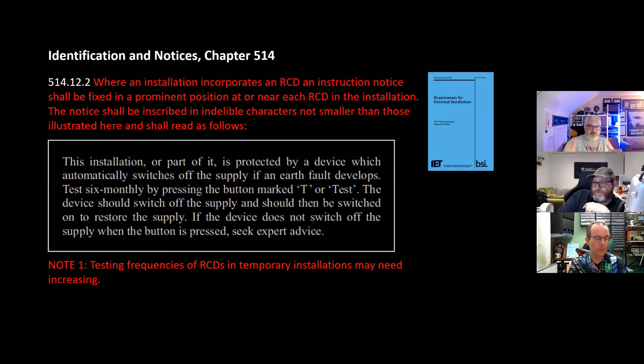However, they've rewritten the reg. An instruction notice of such durable material - maybe someone's learning - as to be likely to remain easily legible throughout the life of the installation, there's an asset management phrase, shall be fixed in a prominent position at or near the origin of every installation. In theory this is a labelling sheet you could put in a switch room, maybe if it's commercial or industrial. The notice shall be inscribed in indelible characters - they've removed 'not smaller than those illustrated here and shall read as follows'.